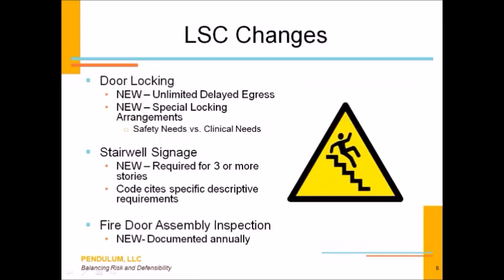When it comes to locking arrangements, there is some relief as well. Previously, under the 2000 edition of the Life Safety Code, you were only allowed to have a single delayed egress locking device in any single means of egress and exit path, meaning you could not have more than one. But again, because of the acknowledgement of the enhancements to building construction and fire protection systems in healthcare facilities, the 2012 edition and newer editions of the Life Safety Code allow you to have unlimited delayed egress within any single means of egress.